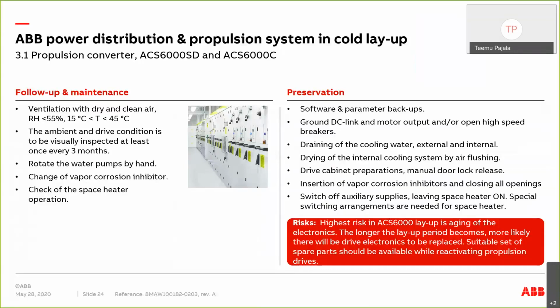And for the 6000 SD drive, the DC link should be grounded, and motor output as well. And on the C, the cycloconverter, the high-speed breakers should be open. And of course, general earthing instructions need to be followed to make all the systems safe to touch, safe to work on. And all the labels, lockout, tagout, like mentioned before. Very important when you cannot be sure where is power, where is not power.